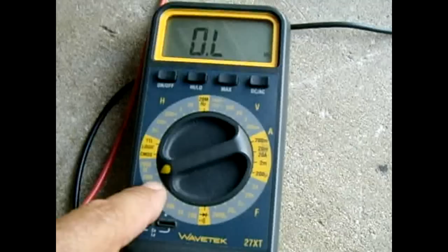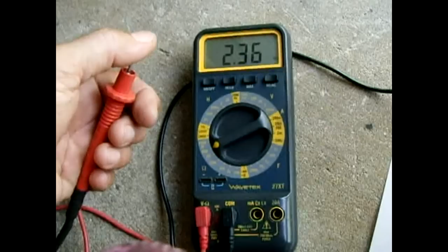Alright, so for the next test, we check the electrode in the middle, that's fine. The next thing you want to do is you want to use a high setting, 20 megohms. I have a 2000 megohm, but the average person doesn't have a meter like this. They have a 20 or a 10, which is fine. And you have to understand when you're doing this kind of a resistance test, let me hold this with my leg, alright? You have to be careful because just your body will give a reading. See, that's coming up 2 million ohms.